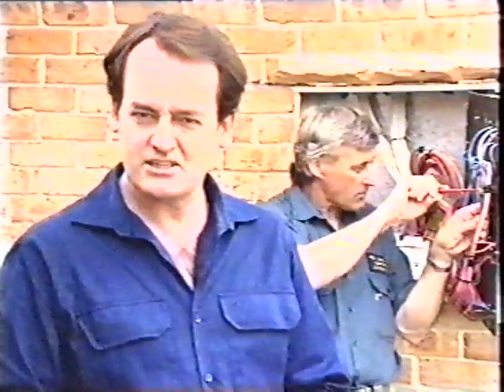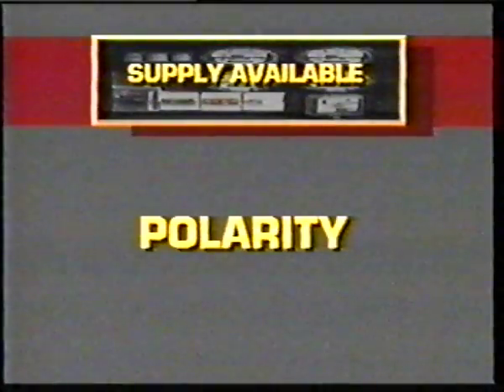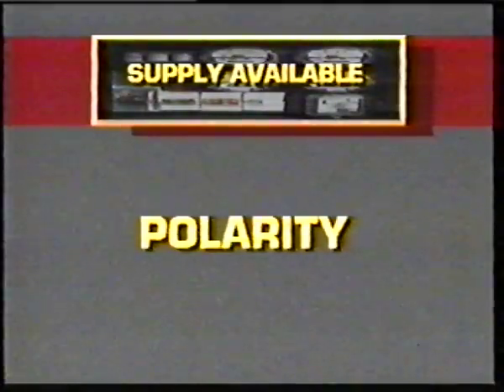Well, we've now demonstrated how the tests can be performed when supply is not available. If supply is available, tests such as polarity, transposition of the neutral and earthing conductors, and interconnection of conductors of different circuits can be carried out. Firstly, the test for polarity, for which we'll need test lamps.